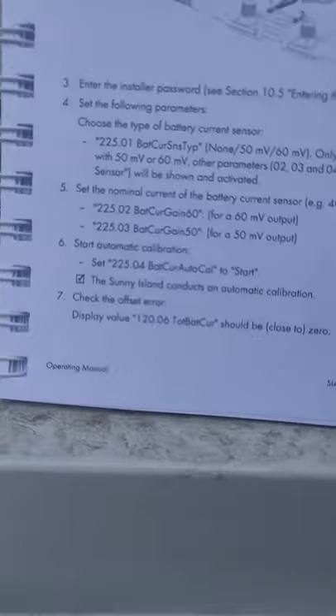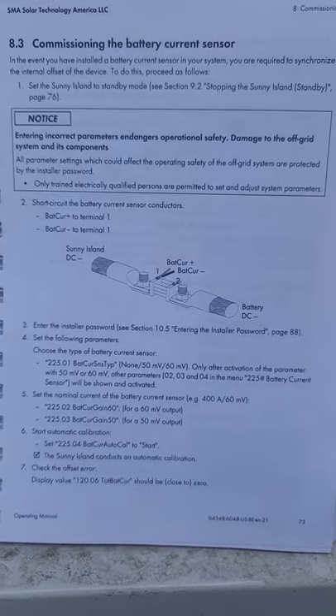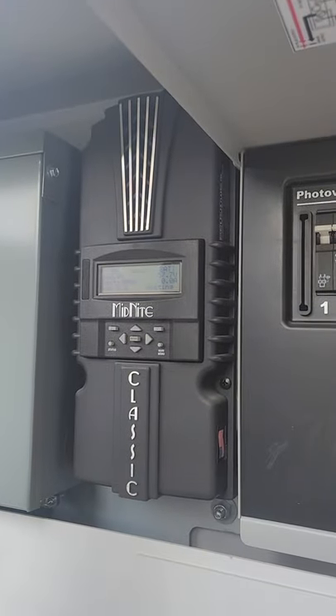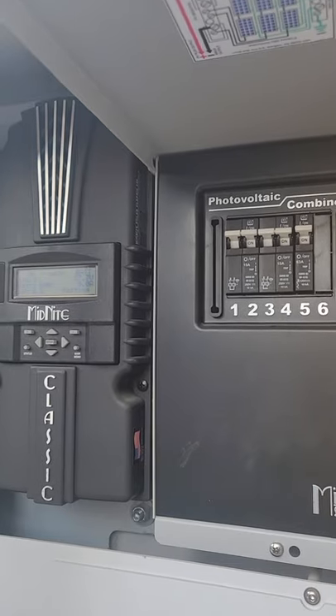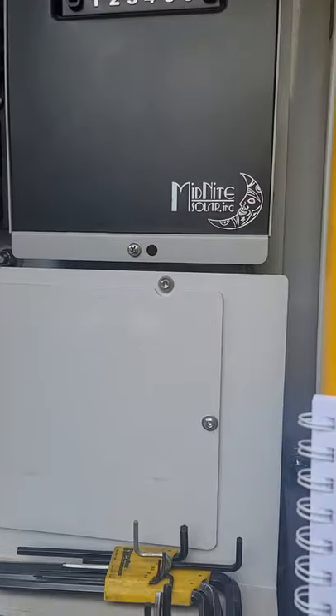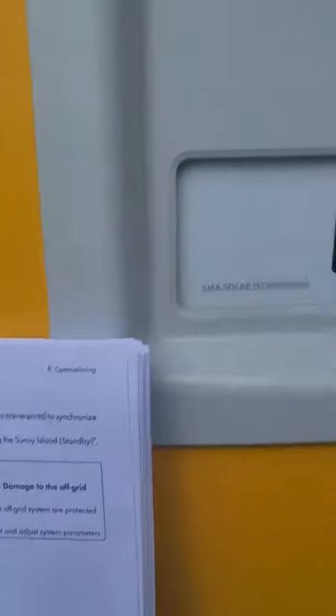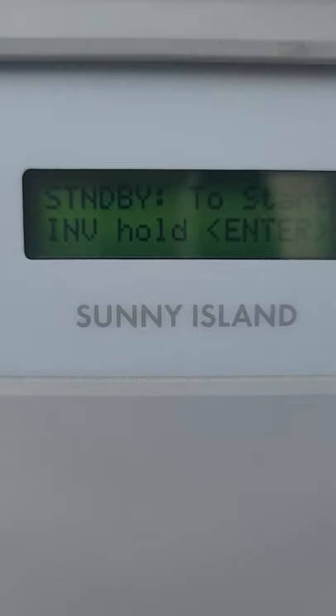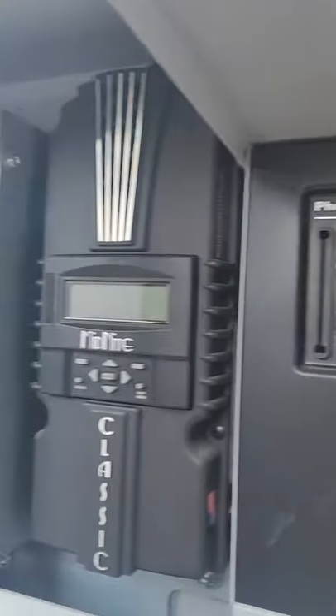On page 73 of the SMA Sunny Island Manual, you'll find the instructions for this. One thing that is not in the instructions is that the MidNite Classic needs to be turned off — that was information gleaned from tech support at SMA. So the first step is to set the Sunny Island into standby mode, which we'll do now. It is now in standby mode, and we're going to turn off the MidNite Classic.